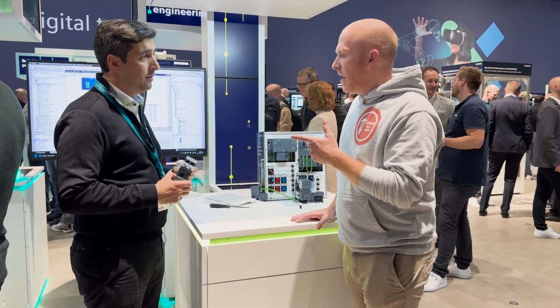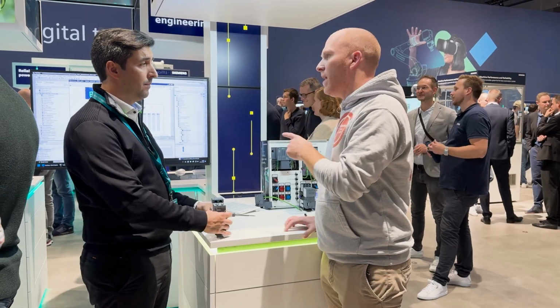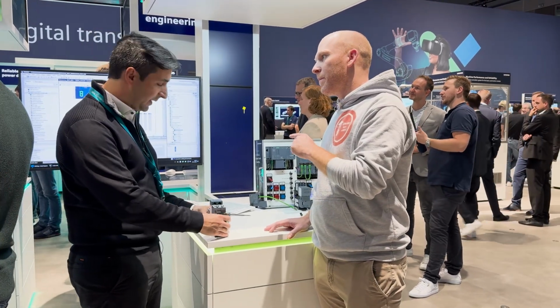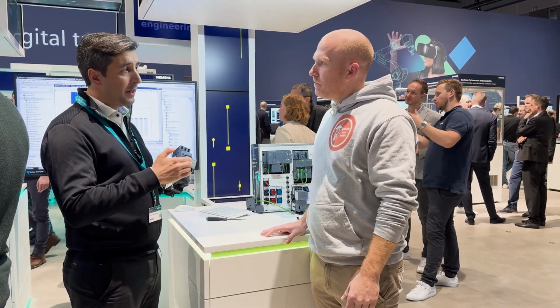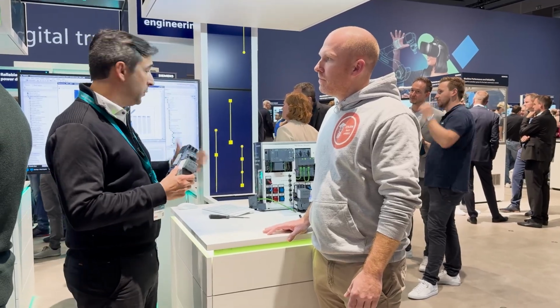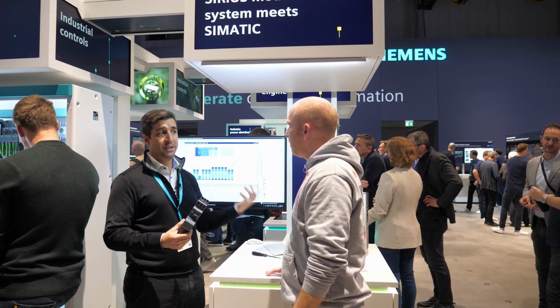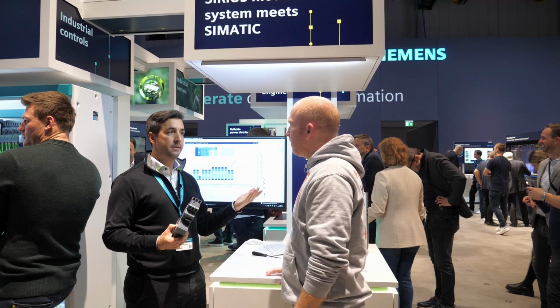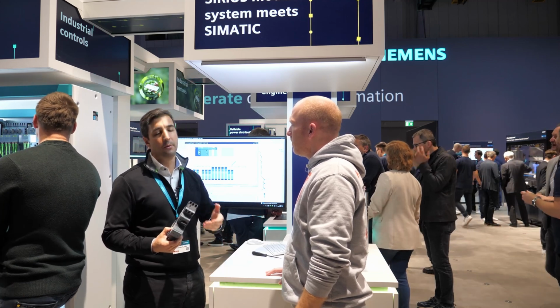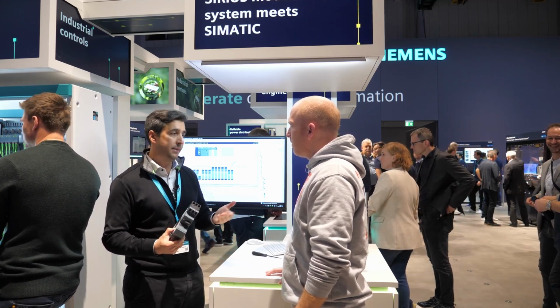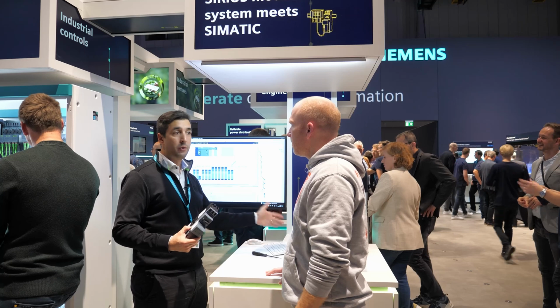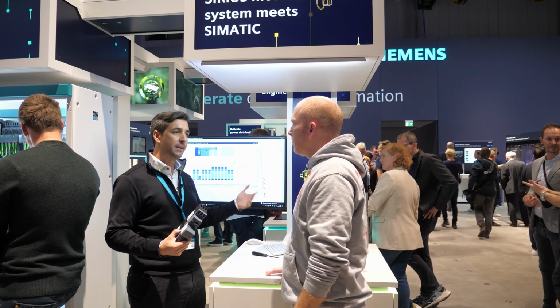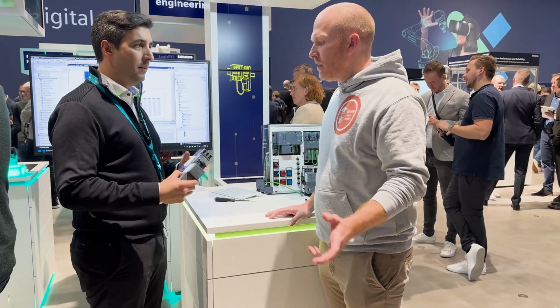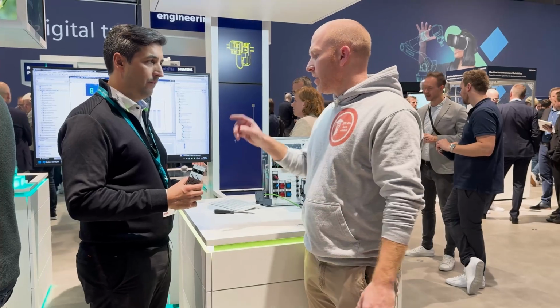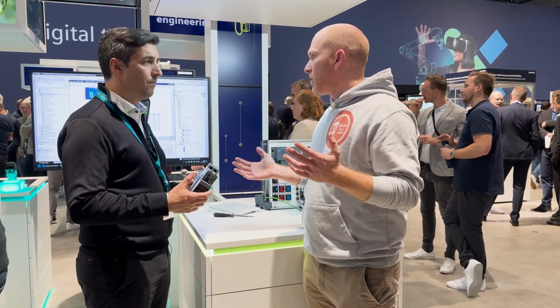Is it right that I saw that you set the current value in the TIA Portal? Exactly. So the configuration of the current that the device is going to work with, you can do in software directly and change it. If you realize that the 10 ampere was not enough and you can go up to 32 amperes with the device, then you just type 12 amperes or 15 amperes, whatever you need, and this will be changed on the device. Yeah, that means for a new project, I just need an MCCB with a standard application.